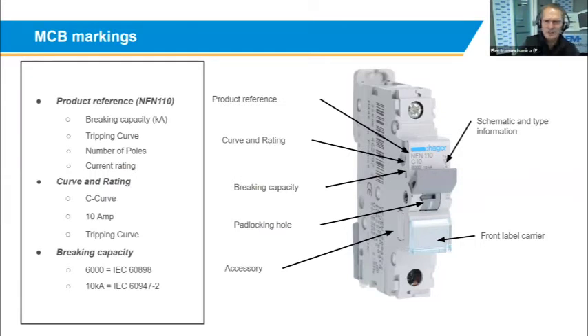If you look at the product reference number, in this case, it's an NFN 110. In that reference number, we know that it's a 10 kA product. We know that it's a C-curve tripping curve on the product. And on the tripping curves, I'll go into a little bit more detail later on what they mean. The NFN in that reference number, I also know that it's a 1 pole. I also know that it's a 10 amp circuit breaker. All of that just in the reference number. But how can we expect the customers to know that NFN 110 means all of that?